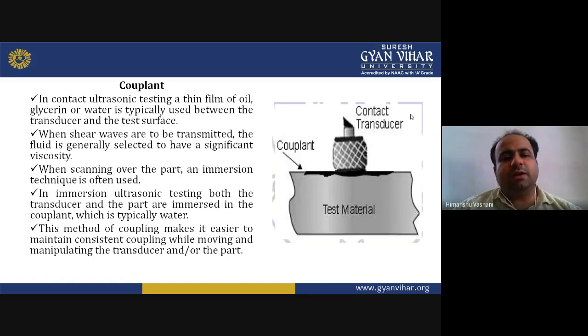Okay. So, in contact ultrasonic testing, a thin film of oil, glycerin, or water is typically used between the transducer and the test surface, or the workpiece surface. Now when shear waves are to be transmitted, the fluid is generally selected to have a significant viscosity. Now when scanning over the part, the immersion technique is often used.